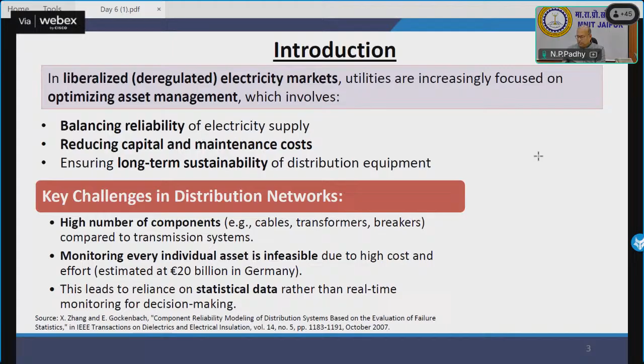So why is failure analysis of network components necessary? First, it supports asset management decisions. Asset management aims to make cost-effective choices for maintenance, replacement, and reinvestment. For these decisions to be accurate, they must be based on historical failure trends and component reliability metrics, which improve supply reliability and power quality. Failures in distribution components like transformers, cables, and circuit breakers directly affect power continuity and customer satisfaction. Understanding when and how components fail helps in taking preventive actions.